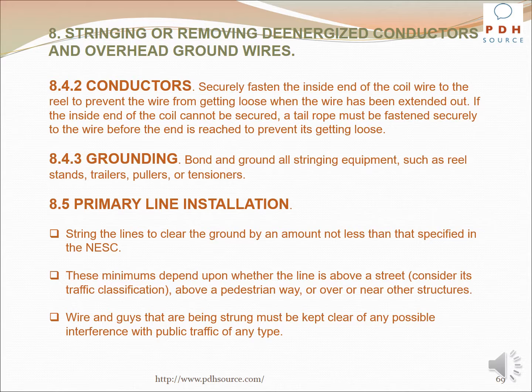Bond and ground all stringing equipment such as reel stands, trailers, pullers, or tensioners. For primary line installation, string the lines to clear the ground by an amount not less than that specified in the NESC. These minimums depend upon whether the line is above a street, considering its traffic classification, above a pedestrian way, or over or near other structures.